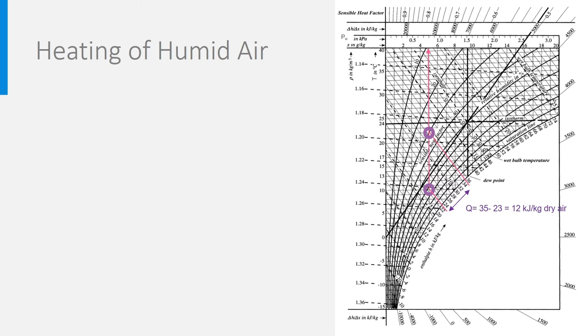If we use the equation from the previous slide, we have for 0.2, H2 is 22 plus 0.005 times 1.86 times 22 plus 2500, which amounts to 34.7 kJ. For H1, we get 22.6 kJ, so the heat needed is 12.1 kJ per kilogram. Of course, reading it on the diagram is a bit less precise, but it is good enough.